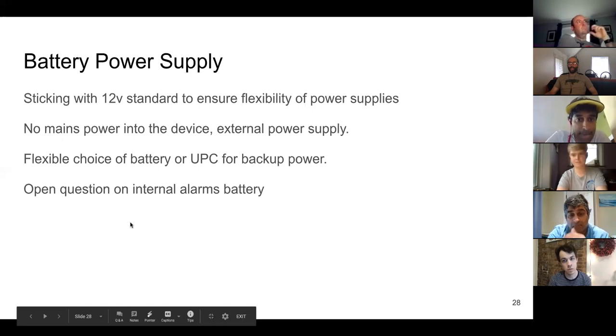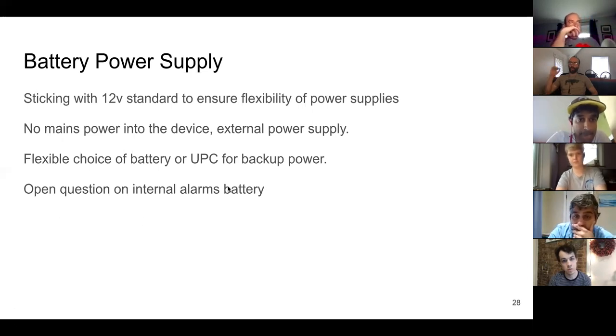My bad. There's also an open question about an internal alarm battery - whether we have a second, much smaller battery in the device that can't run the ventilator but is enough so that if there's a power outage, the vent doesn't just go silent and dead.